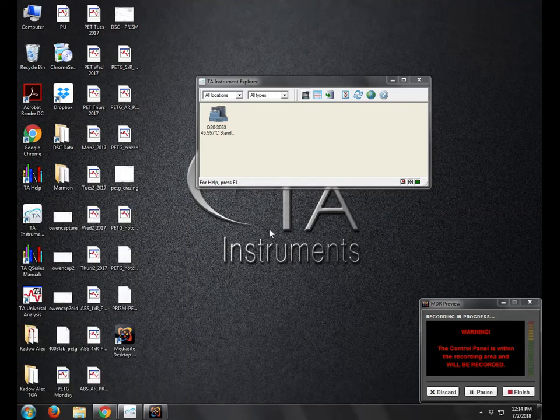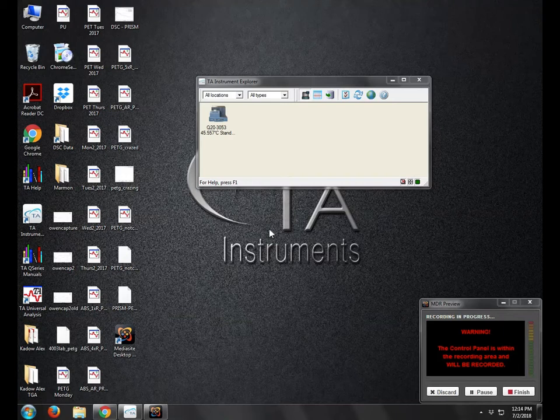There is a power switch on the back of the DSC, which we've switched on. We've waited about two minutes, and there's a green light in the front of the instrument that should be on, and it should beep when it is also on after that time.